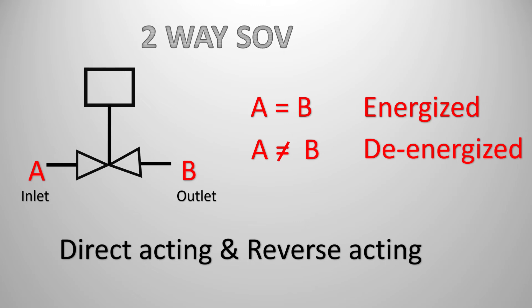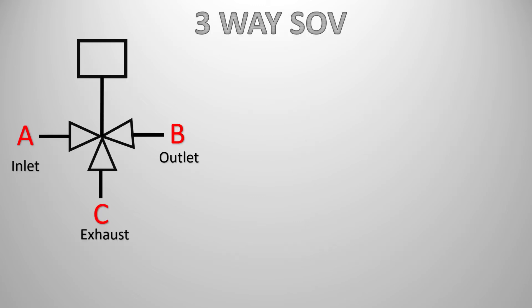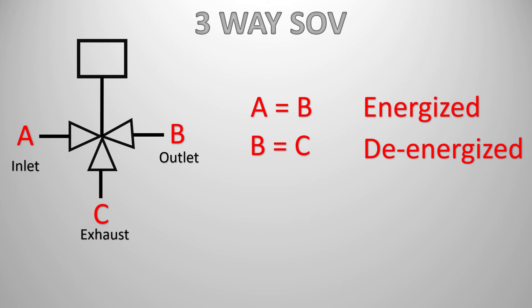Similar to the two-way solenoid valve, there is a three-way solenoid valve which has three ports: an inlet port, an outlet port, and a third exhaust or vent port (port C). When the coil gets energized, the inlet and outlet ports connect — A equals B. When the coil de-energizes, the outlet port connects with the exhaust or vent port (port C). This means that process medium — air, gas, or hydraulic fluid — which went into the outlet port will vent or exhaust through the exhaust port when de-energized.